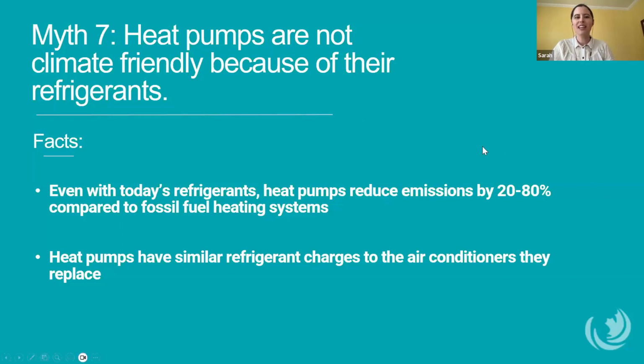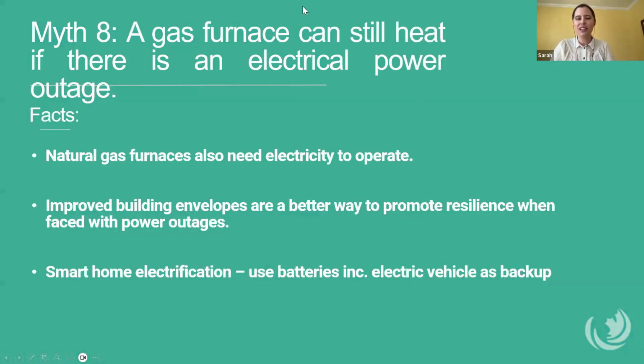So on to myth 8, a gas furnace can still heat if there's an electrical power outage. In the event of a power outage, there's this idea that a heat pump wouldn't work while a gas furnace would, which might make some people want to stick with fossil fuels. However, a furnace fueled by gas is also dependent on electrical fans that push the waste products from the combustion process out the flue. Without this, occupants could actually experience carbon monoxide poisoning, which is very serious. Therefore, the furnace's built-in safety system doesn't allow it to run during a power outage either.